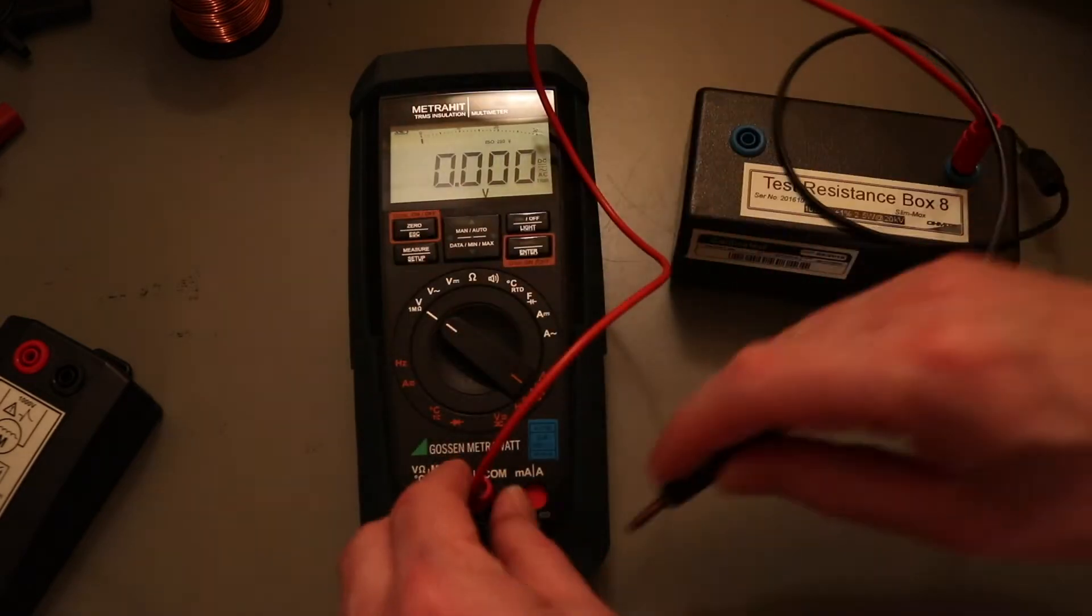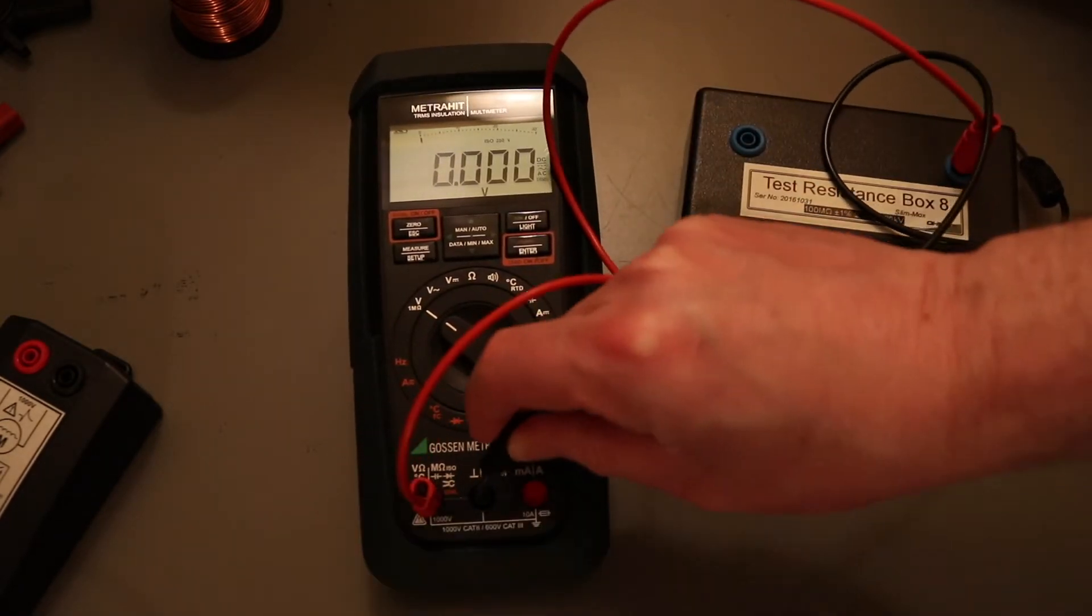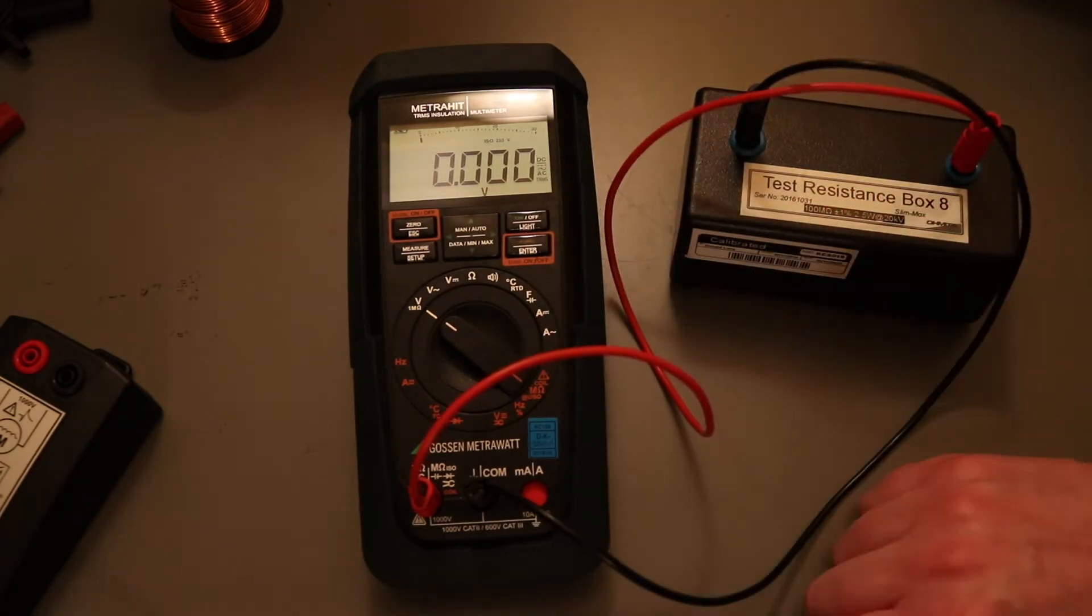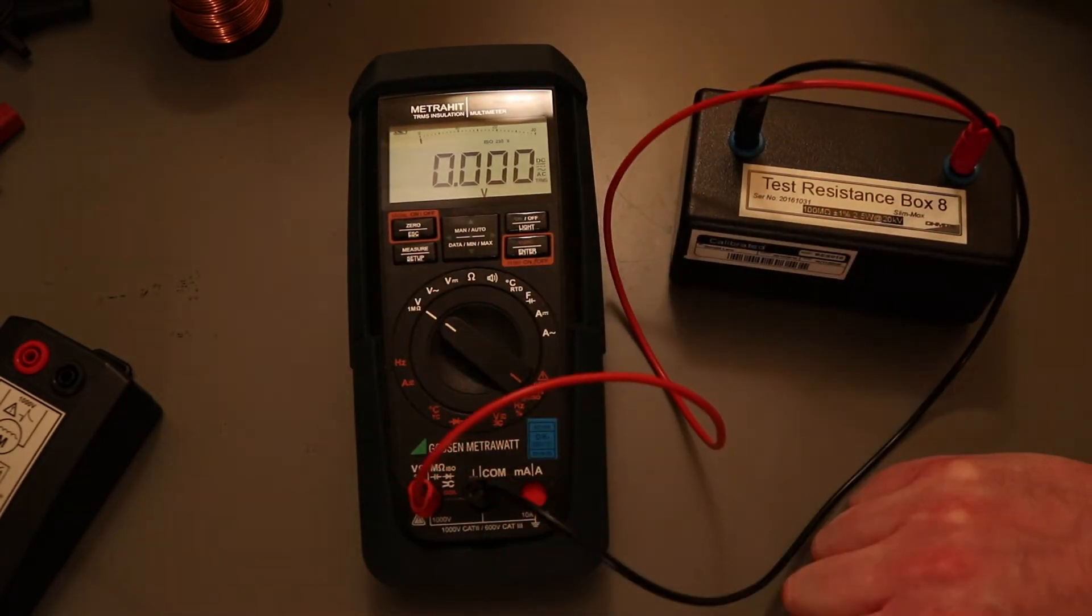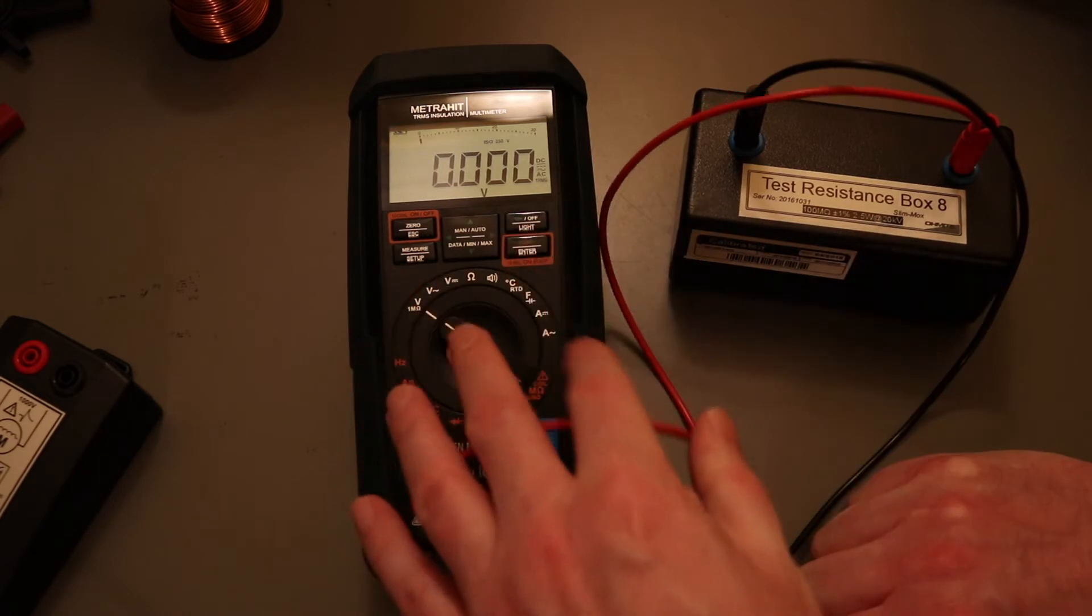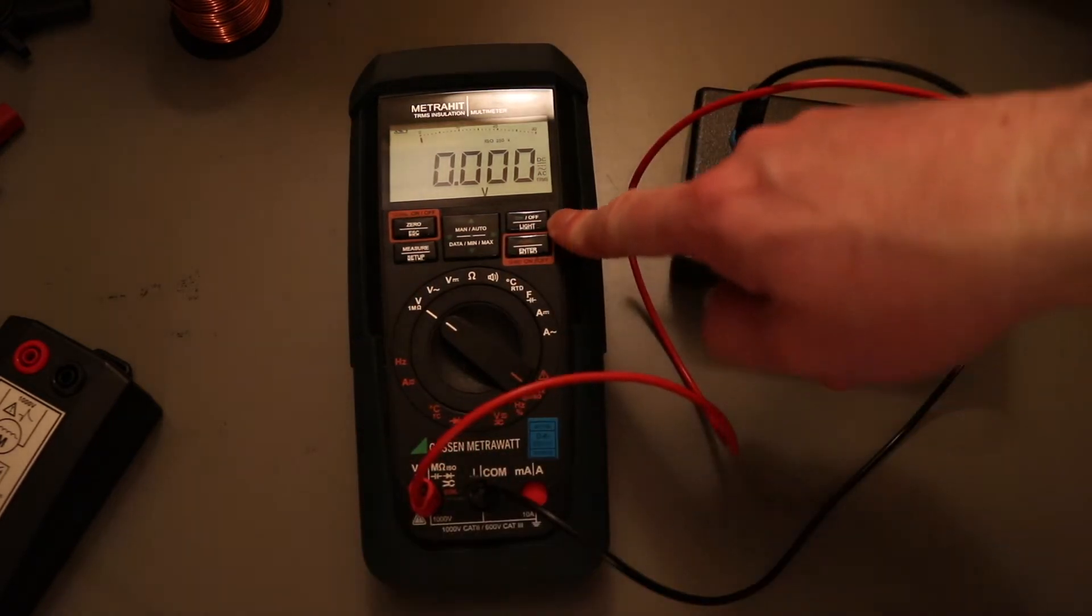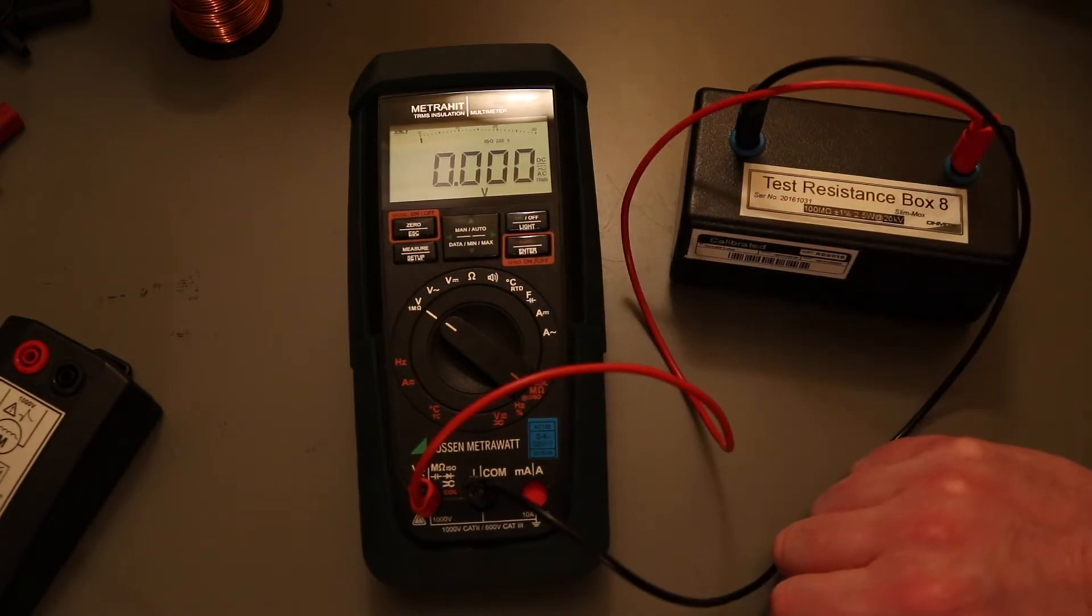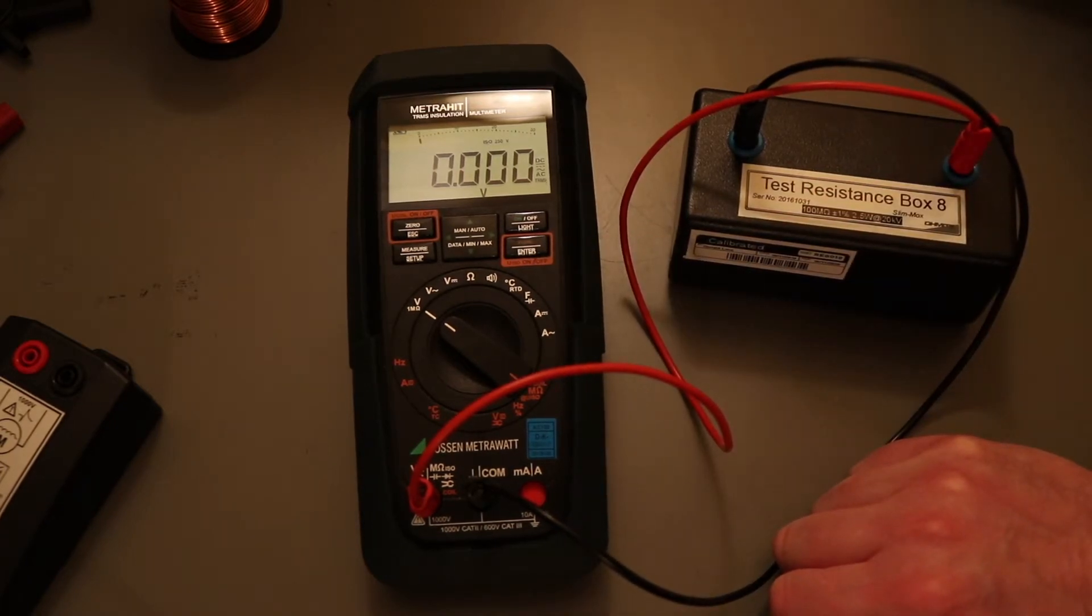Now the meter differs in that it doesn't actually have much of a lock-on function for doing an insulation test. It also doesn't have DAR or PI timed ratios built into the instrument either. If you wanted to do those you'd have to physically hold the insulation test button in for the duration of that test. So that to me is really missing.